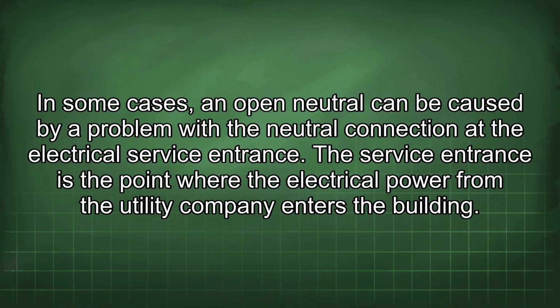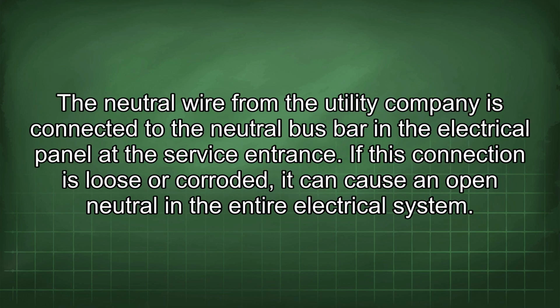In some cases, an open neutral can be caused by a problem with the neutral connection at the electrical service entrance. The service entrance is the point where the electrical power from the utility company enters the building. The neutral wire from the utility company is connected to the neutral bus bar in the electrical panel at the service entrance. If this connection is loose or corroded, it can cause an open neutral in the entire electrical system.